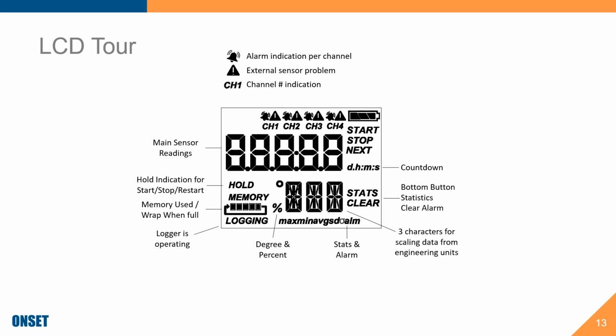There's a countdown if you're doing a delayed start. The top button is mainly used to do a push-button start or stop, or to scroll through each of the channels. A bit of a change here is that we don't show all 4 channels at once on one screen — you need to use the push button to go through the different channels to see their readings.